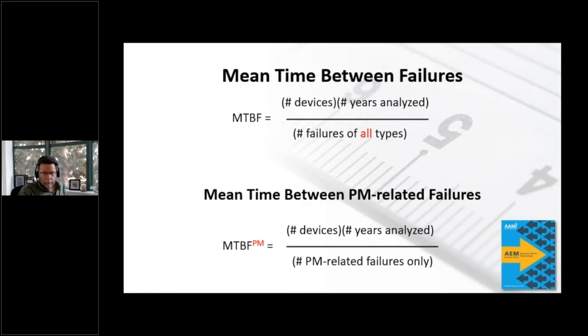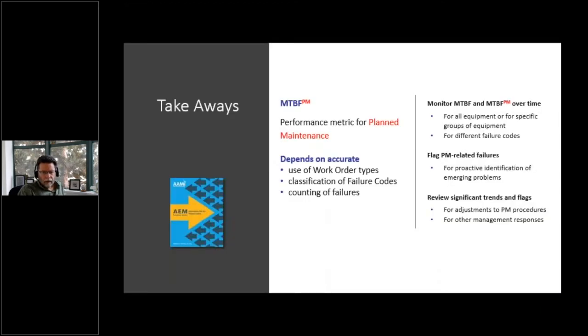So, next slide. This is the sort of thing I was talking about in the previous slide. What you want to monitor is both MTBF and PM-related MTBF over time, across different kinds of equipment. For example, you might want to track certain infusion pumps because they have plenty of failures to be attended to. And for different failure code types, you might want to monitor failures related to programming, failures related to no problem found, and all sorts of other analyses you can do once you've got some granularity in your failure code data.